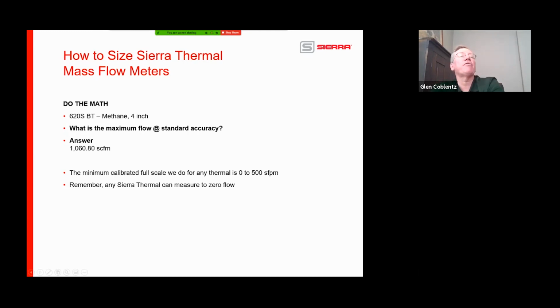So if you did the math there, you find out what the maximum flow rate is. And remember, any Sierra thermal can measure zero flow. So if in this particular application, the customer said, well, I think my flow rate is 800 SCFM. Perfect, no problem. We are going to calibrate it 0 to 800.